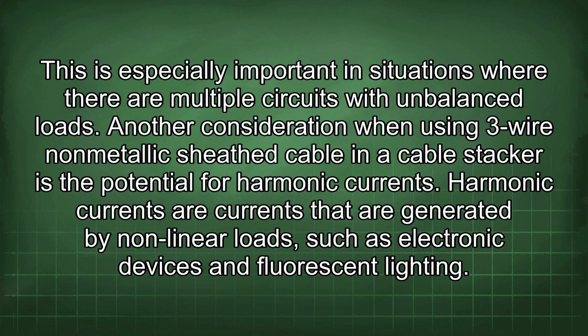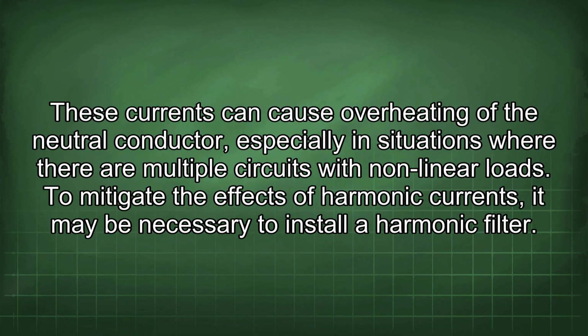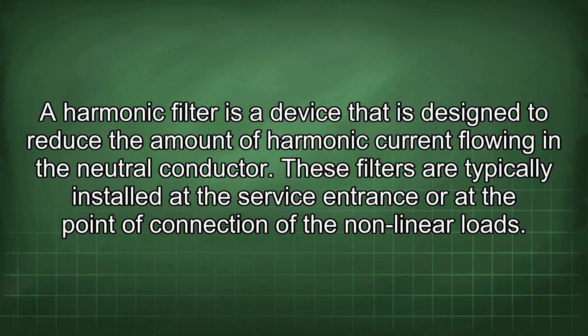Another consideration when using 3-wire non-metallic sheath cable in a cable stacker is the potential for harmonic currents. Harmonic currents are currents that are generated by nonlinear loads such as electronic devices and fluorescent lighting. These currents can cause overheating of the neutral conductor, especially in situations where there are multiple circuits with nonlinear loads. To mitigate the effects of harmonic currents, it may be necessary to install a harmonic filter. A harmonic filter is a device that is designed to reduce the amount of harmonic current flowing in the neutral conductor. These filters are typically installed at the service entrance or at the point of connection of the nonlinear loads.